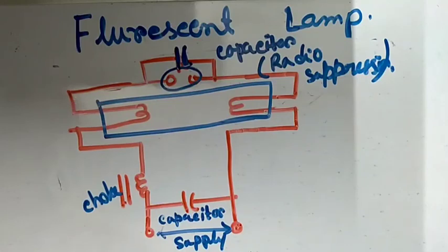Now, a fluorescent discharge lamp may be operated on a DC supply also, and this requires the use of a resistive ballast for arc stability in addition to the choke for producing the voltage pulse, and the resistive ballast introduces very high power loss. Also, the migration of positively charged mercury ions towards the cathode results in low light output from the anode end of the tube, and for this reason, whenever the tube is to be used on DC, a reversing switch is normally used in the circuit to change the direction of the current through the tube every few hours.